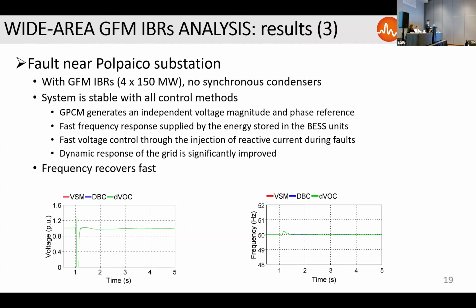Now, in the second test, instead of synchronous condensers, they included the grid-forming converters with a capacity of 150 megawatt. They were operating at 100 megawatt before the fault, so there was some power flow before the fault. They were not just turned on as a corrective measure. With all three control modes that we were discussing at the beginning of the second part of the presentation, the system is stable, we get very similar responses, and the frequency stabilizes much faster after the fault clearance. So we can see that with the much reduced capacity, previously we needed 1100 megavar for the synchronous condensers, and now it's only 600 megawatt of the grid forming converters.